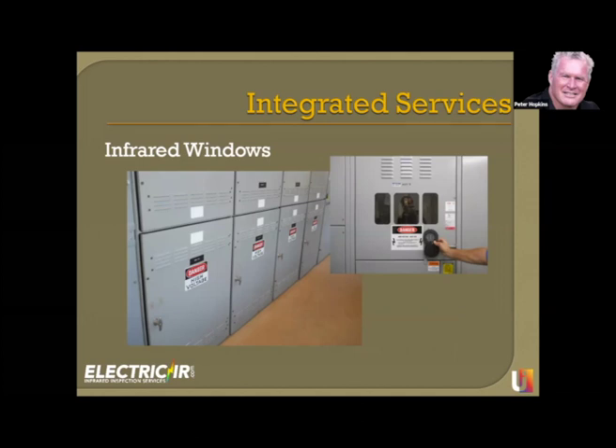So I'm just giving you an example - this is a university located in the San Diego area that we were helping with IR windows. We're basically showing where their switchgear is - we're going to put in one or two windows in this panel. They use what's called a Greenlee, which is a press. They'll take the metal cover off during a maintenance window, then press a hole into that metal and install this window.